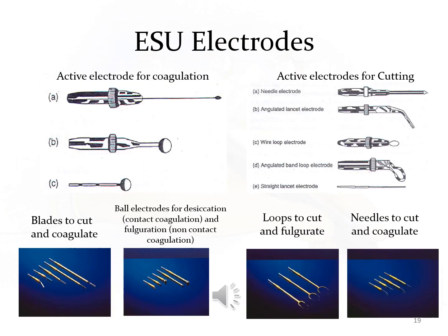Electrodes are connected to the radiofrequency power generator. Active electrode: small size, 1 millimeter in thickness and a width of up to 10 millimeters. The figures represent active electrodes for coagulation and active electrodes for cutting.